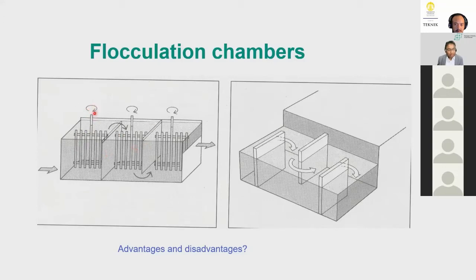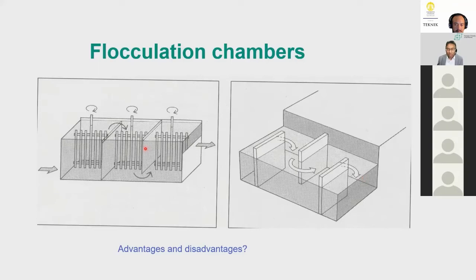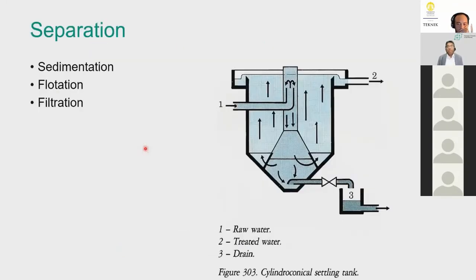Instead of paddle flocculators, some treatment plants have adopted channeled flocculators: walls are arranged so water first flows faster through narrower gaps, then progressively slower as the gaps widen, emulating the flocculation chamber effect. This design has become much more common. After flocculation, water containing flocs must be separated — there are three separation methods: sedimentation, flotation, and filtration.